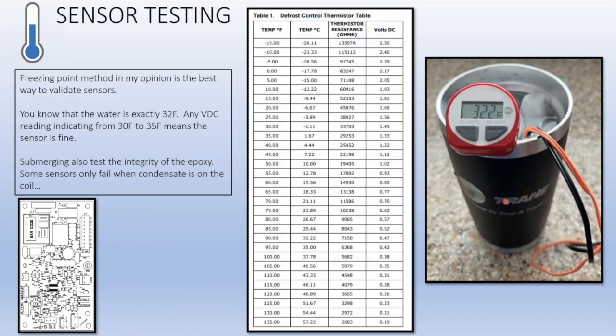So verifying those sensors, in Service Facts, you're going to see a chart. It's going to have temperature in Fahrenheit and Celsius that goes along with a resistance, because these are thermistors. And if it's connected to the board, you would use volts DC, and I'll show you guys that here in a second. So what I recommend is put your sensors in ice water, fill the cup with ice or vessel with ice, and backfill with water. Then you know that it's 32 Fahrenheit in that cup, right?